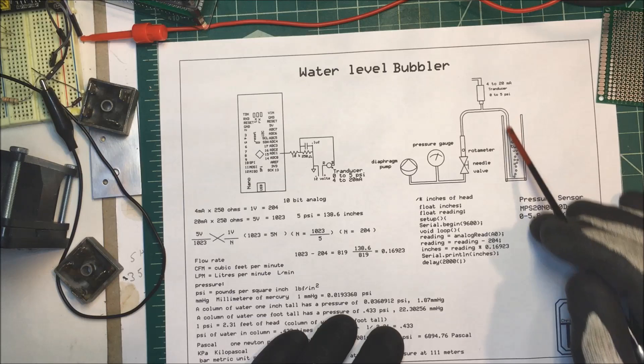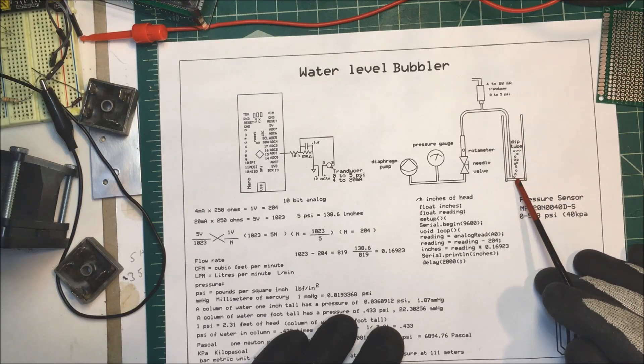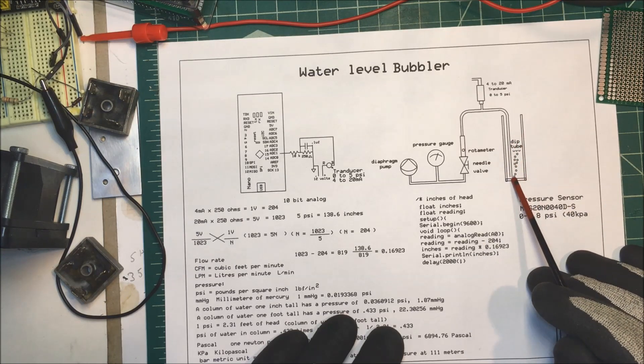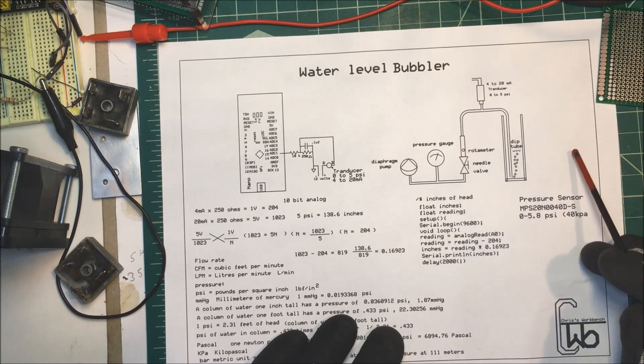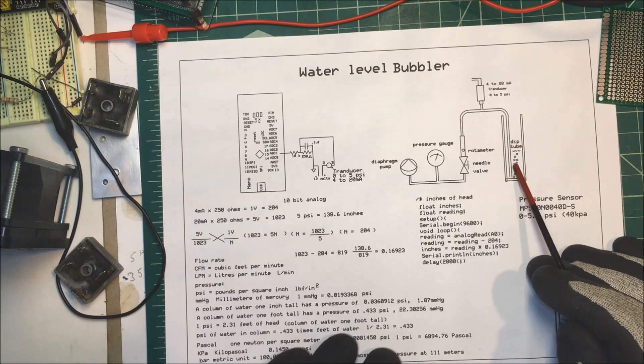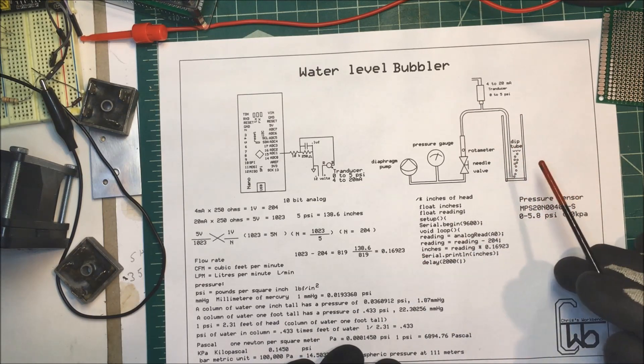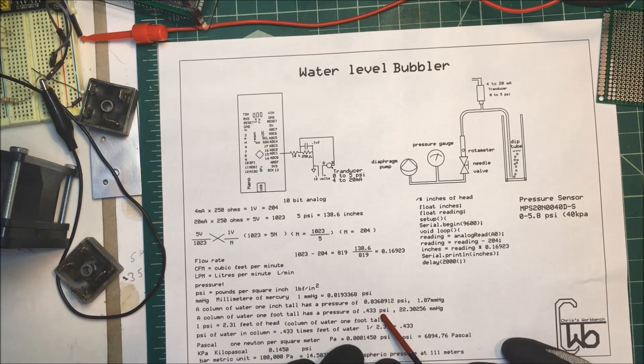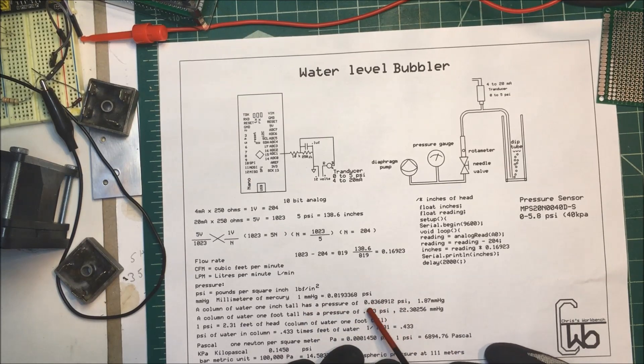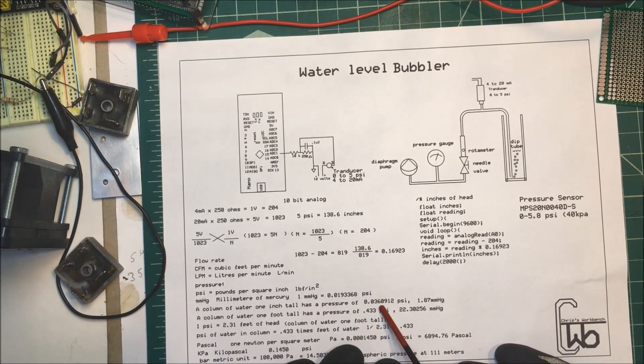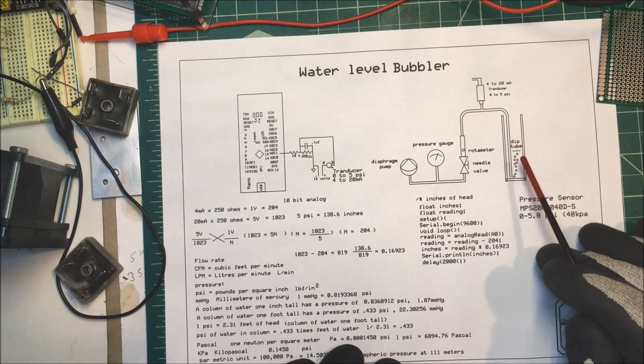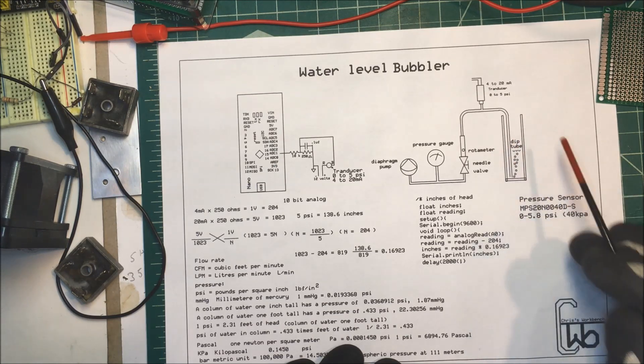Now the air goes down to the bottom of the system here and the water here is going to create a pressure on this tube here. And we're going to read that pressure here. Now, a column of water one foot tall has a pressure of 0.433 psi. And a column water one inch tall has a pressure of 0.03609 psi. So we can use that pressure to determine the height of the water, the level.